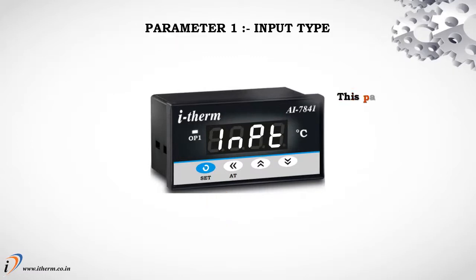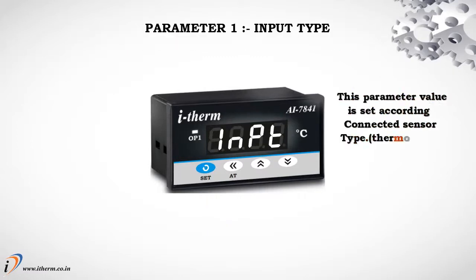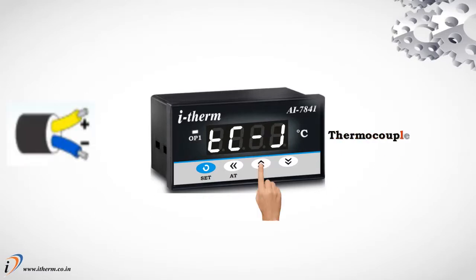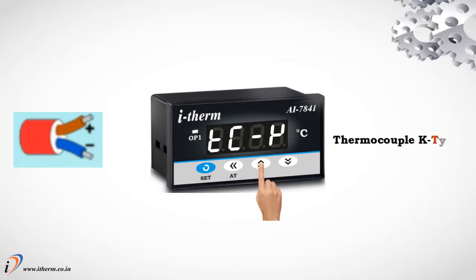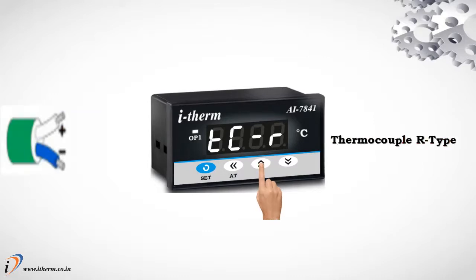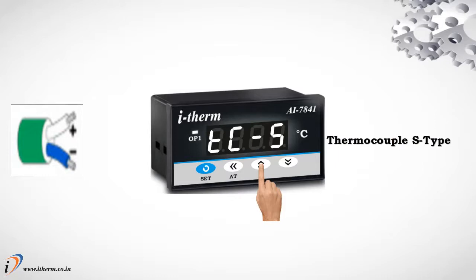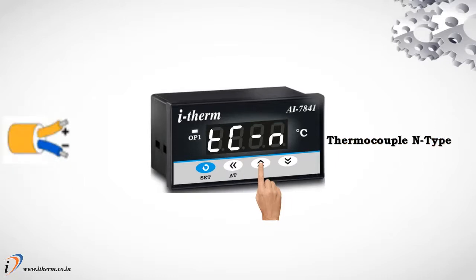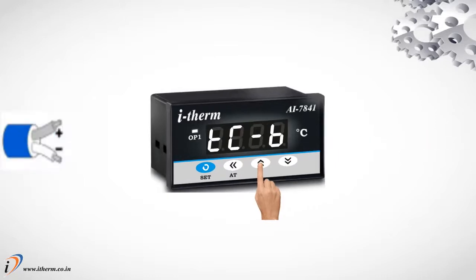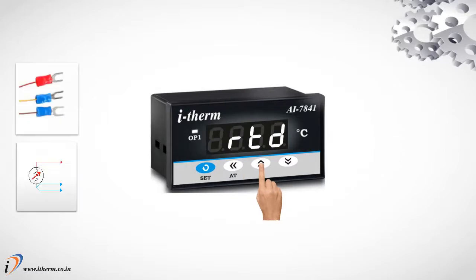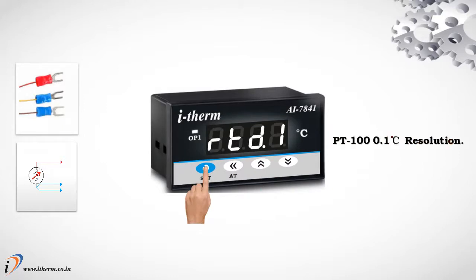Parameter 1, Input Type. This parameter value is set according to connected sensor type. Thermocouple J type. Thermocouple K type. Thermocouple R type. Thermocouple S type. Thermocouple N type. Thermocouple T type. Thermocouple B type. PT 100 at 1 degree centigrade resolution. PT 100 at 0.1 degree centigrade resolution.